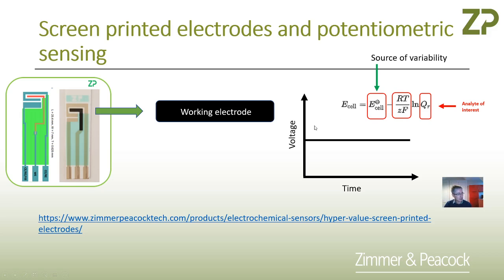So those were some comments about using screen printed electrodes for potentiometric sensing. If you want to make good progress using screen printed electrodes for potentiometric measurements, you probably have to do a single-point calibration so you at least know what the offset value is. Any questions — contact us at Zimmer and Peacock. Thanks very much.